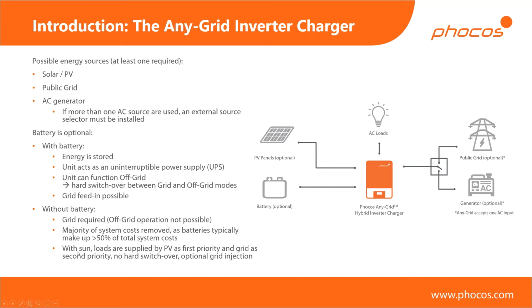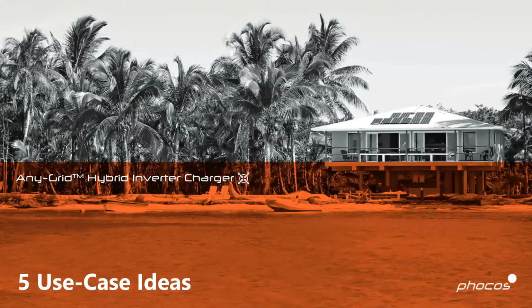And then finally, if you're working without a battery, you can still obviously take advantage of your PV power. And if you do have any excess energy, so if you're producing more power from PV than you require for your AC loads, then it's up to you if you want to inject that into the grid or not. So there's a specific setting for that. If you're not allowed to inject into the grid, for example, then you would just leave that disabled. So now I'll move to the 5 use case idea.